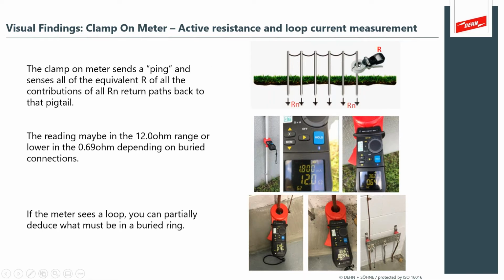It only looks at that one pigtail. So this is where it's very important to understand what you're evaluating. It gives you an indication, but in and of itself, it is not a pass-fail unless you know what you're looking for. So if I know I'm looking for a buried connection, and if I know that I should be connected to buried rings, I should get a 0.69, a 0.64 reading.